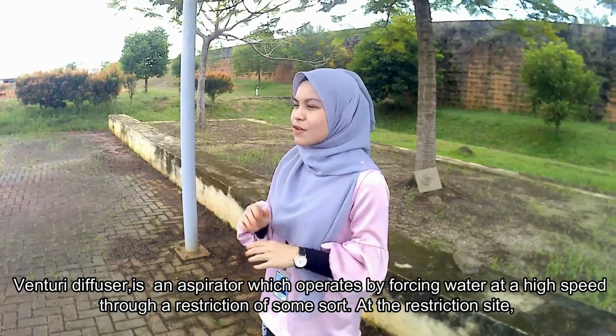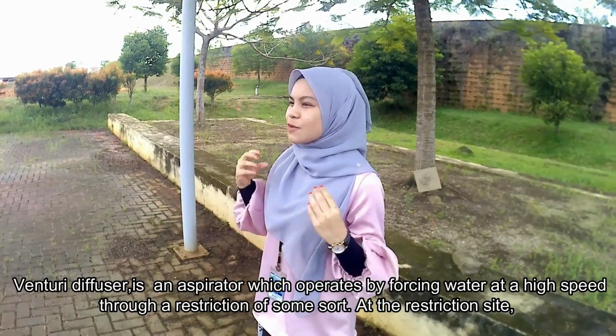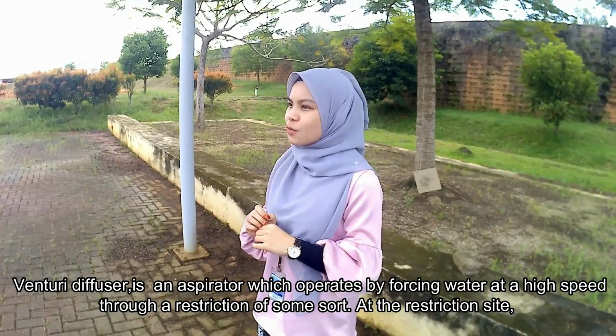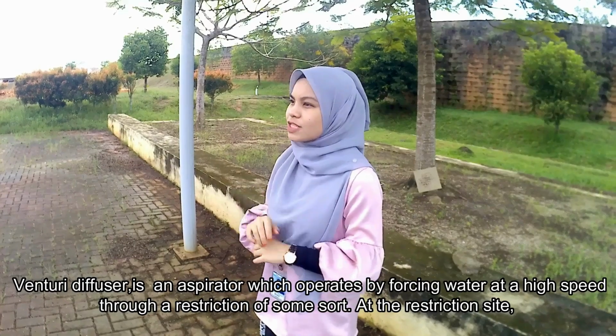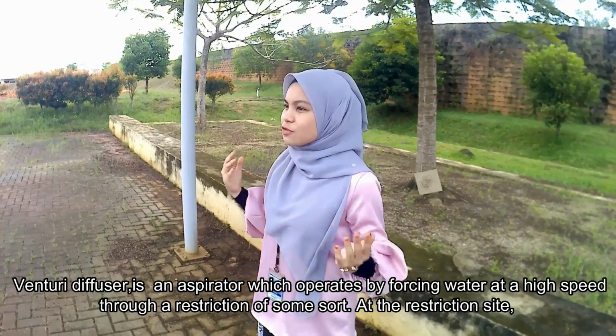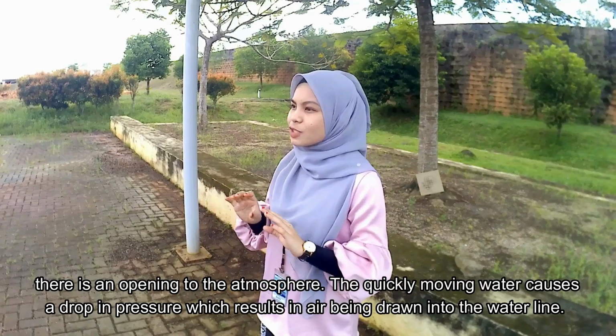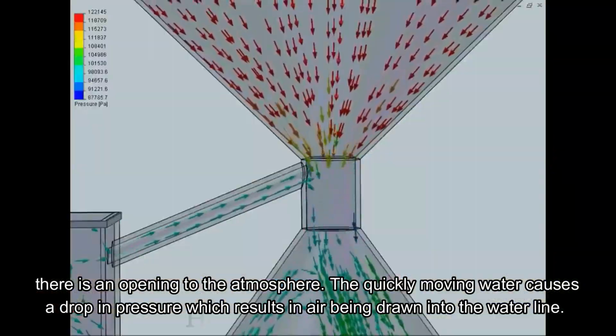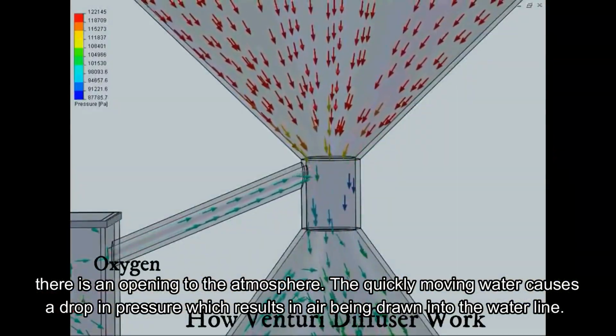Venturi diffuser. A venturi diffuser is an aspirator which operates by forcing the water at high speed through a restriction of some sort. At the restriction site, there is an opening to the atmosphere. Quickly moving water causes a drop in pressure which results in air being drawn into the water line.